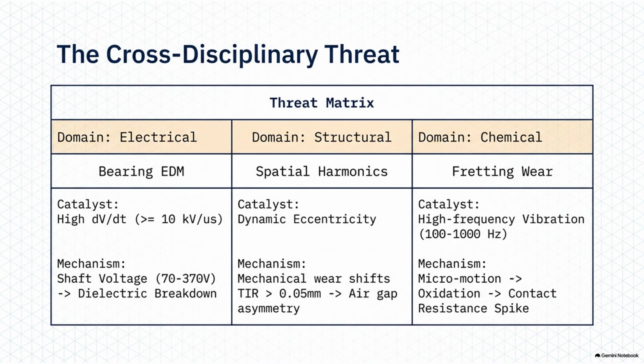Wow. Engineers actually measure this voltage change rate as dVdt. And in these high-performance systems, we are looking at a dVdt of 10 kilovolts per microsecond. Wait, let me just pause on that number for a second because the scale is kind of hard to wrap your head around. It's massive. 10 kilovolts is 10,000 volts. And it is shifting that massive amount of pressure in 1 microsecond, a millionth of a second. Yes, the sheer violence of that electrical shift must have massive side effects.